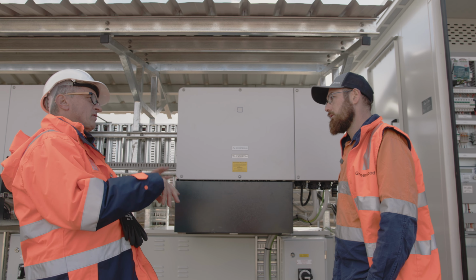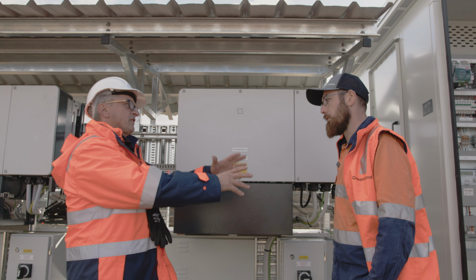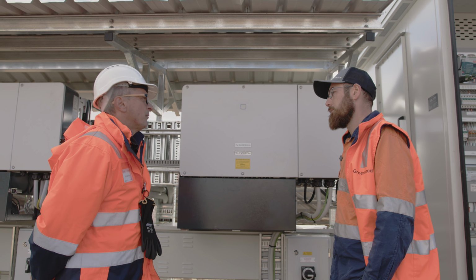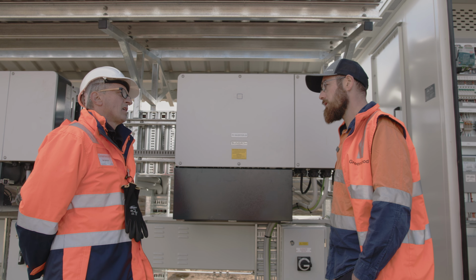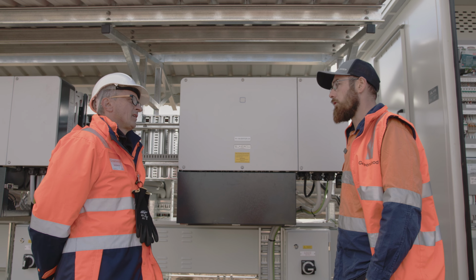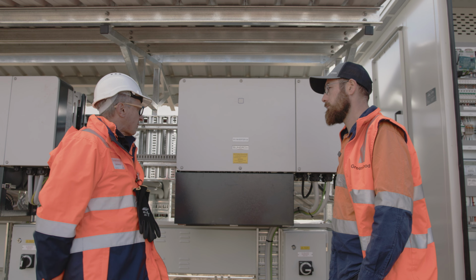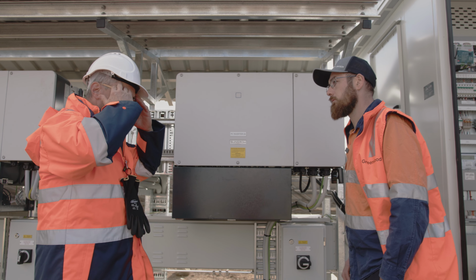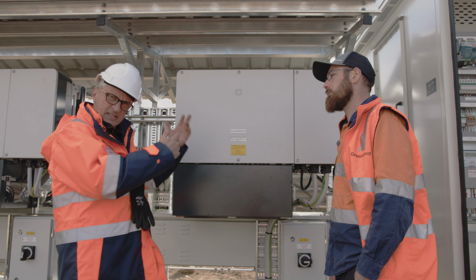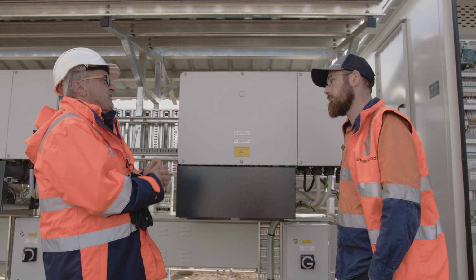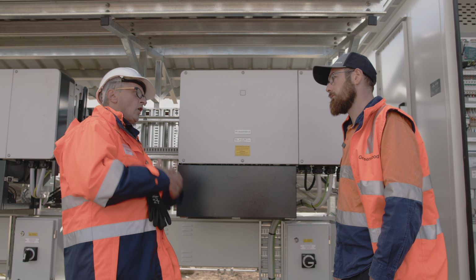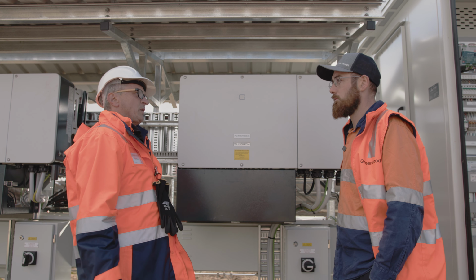And that's voltage at maximum power point? No, that's VOC, not maximum power point - at maximum power point it'd be slightly less, probably bringing you right into the optimum range for this unit. And the VOC max obviously refers to the VOC off the data sheet, but VOC max takes into consideration the coldest temperatures a site like this would experience.